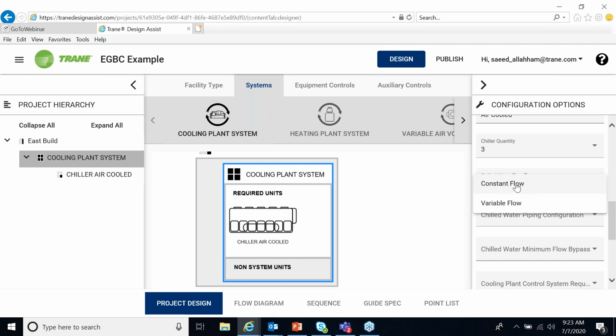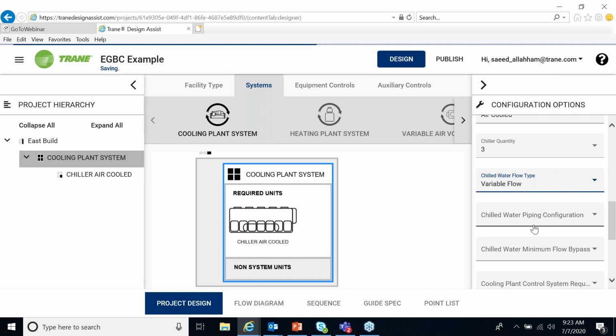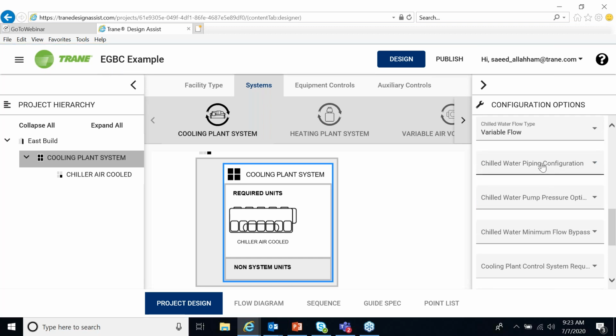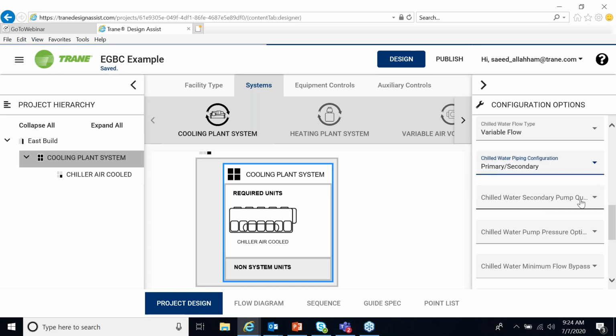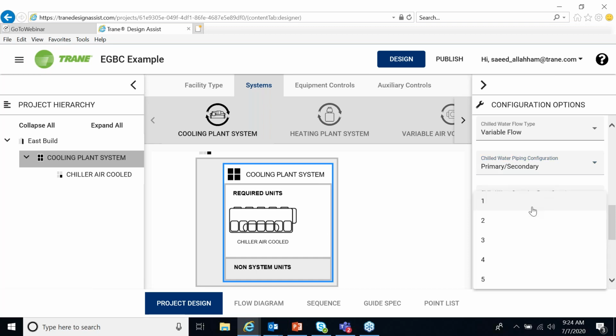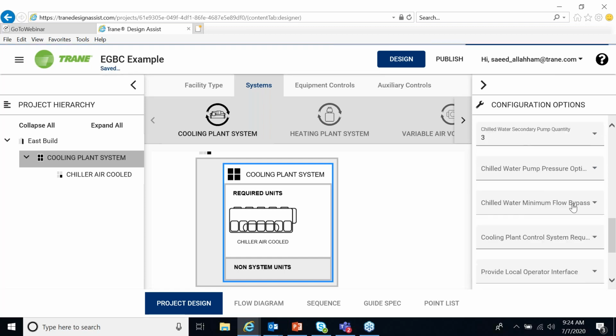The flow that is going to the load side, is it constant flow or variable flow? Let's say variable flow, which is more common. A chilled water configuration, is it variable primary or primary secondary? Let's say primary secondary. By doing this, you are making the configuration of the control for the cooling plant system that you have. How many secondary pumps do you have, 1, 2, 3? Let's say we have 3 pumps in the secondary.